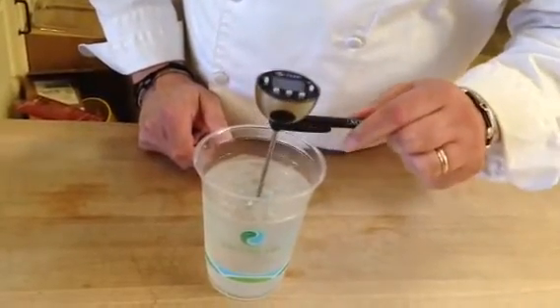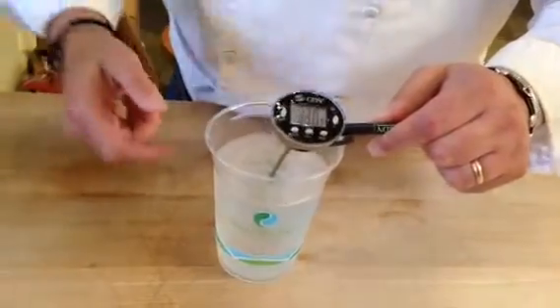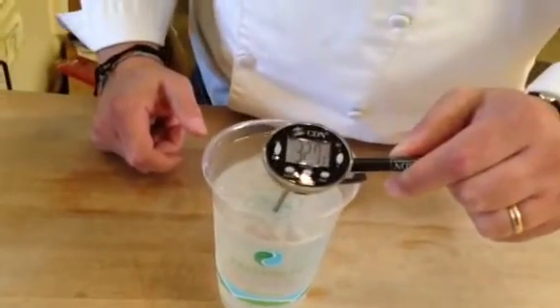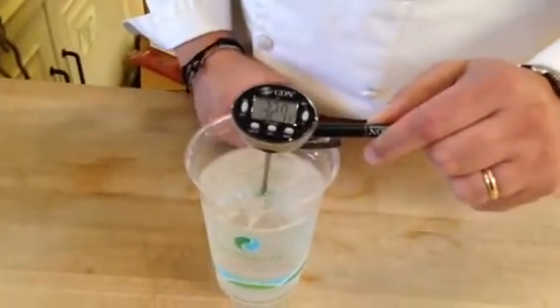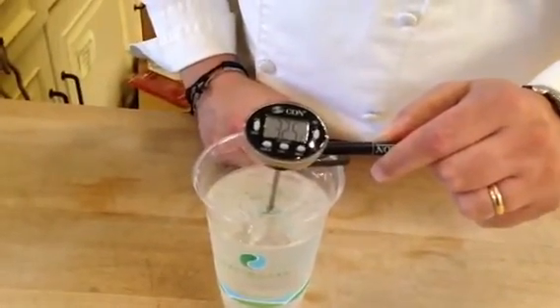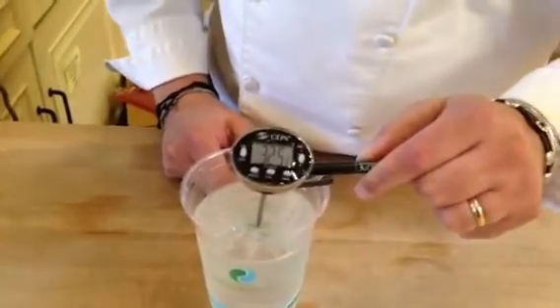You want to give it about a minute and see. This has a pretty quick response time, as you can see. You want to hold it in there for a minute and make sure that it holds temperature between 30 and 34 degrees, because you want a plus or minus 2 degree differential as acceptable.